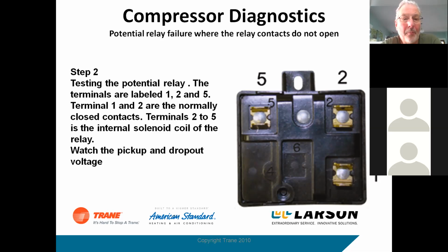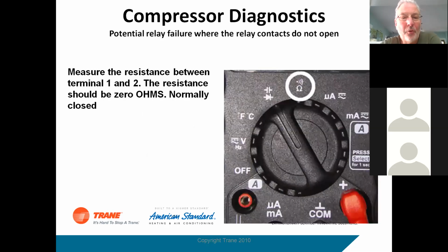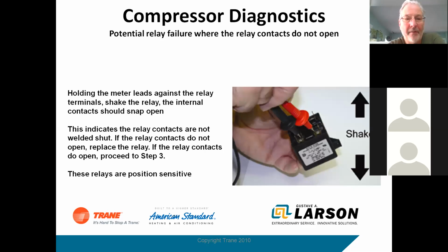If you want to test them, the terminals are labeled 1, 2, and 5. Terminal 1 and 2 are normally closed contacts, and that's what goes to the start winding. And then as the compressor starts and the voltage comes up, it opens that contact and it pulls that start capacitor out of the circuit, okay? Measure the resistance between 1 and 2. It should be 0 ohms. So terminal 1 and 2 are your normally closed contacts, and that should read 0 ohms. It should be like a closed contact.